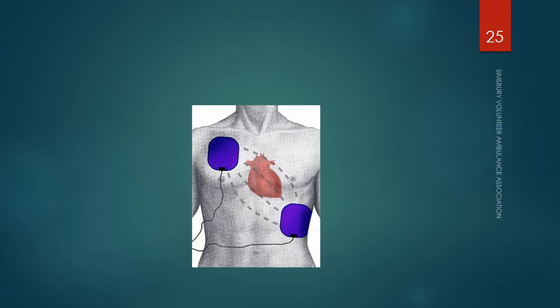Now, when you stick it to the patient, sometimes there's a little bit of a challenge. Maybe the patient has a lot of adipose. Maybe the patient has extremely large breasts. Maybe the patient's extremely thin. But the goal is to make sure those pads are in contact with the skin. So if you have someone that has some rolls or layers of flab, you need to flatten that out so that there aren't any lumps or bumps or rolls before you place the pad there. Because if you have gaps and the pad does not have complete contact with the skin, you are not going to be delivering the amount of energy necessary to stop whatever the lethal rhythm is that caused the patient to go into cardiac arrest.